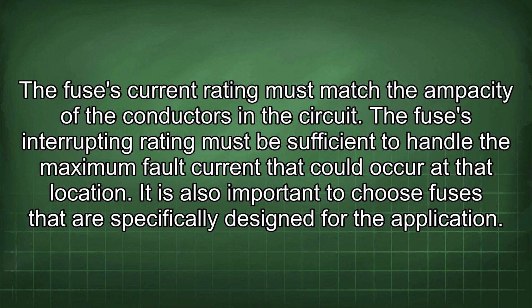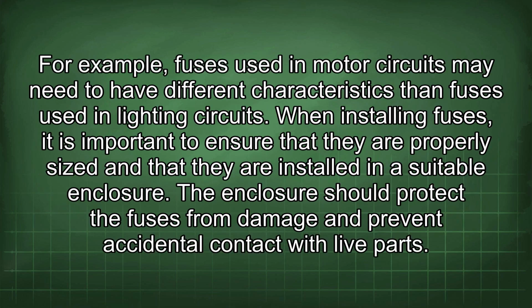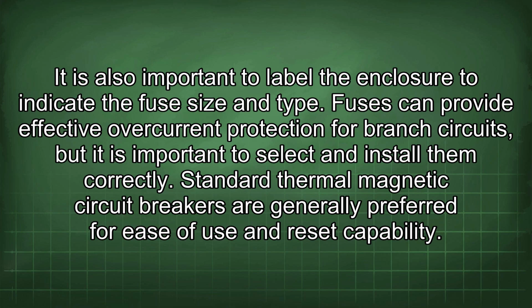It is also important to choose fuses that are specifically designed for the application. For example, fuses used in motor circuits may need to have different characteristics than fuses used in lighting circuits. When installing fuses, it is important to ensure that they are properly sized and that they are installed in a suitable enclosure. The enclosure should protect the fuses from damage and prevent accidental contact with live parts. It is also important to label the enclosure to indicate the fuse size and type.